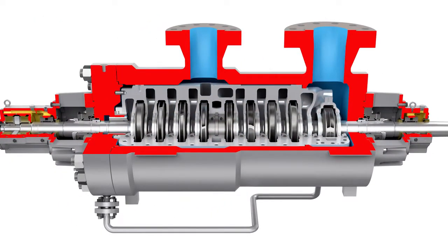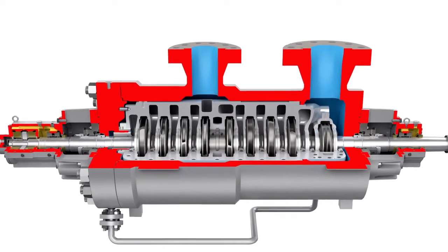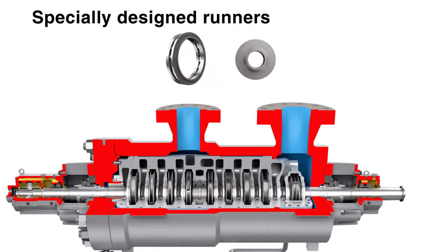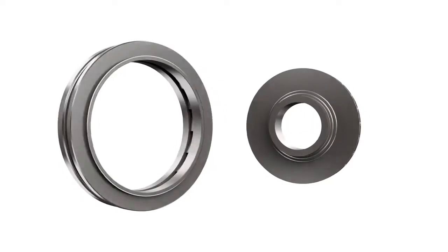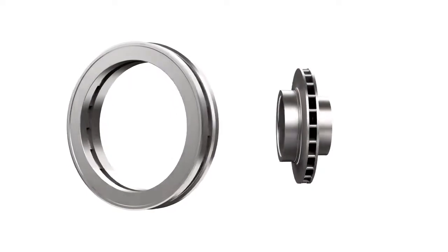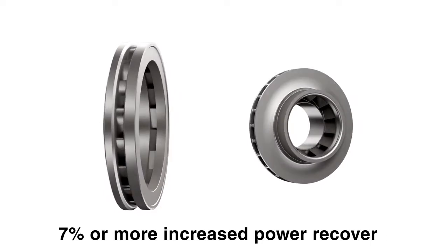Traditional HPRTs, which are essentially pumps running in reverse, may not be able to take advantage of this. But by employing a turbine design that can accommodate the change in volumetric flow rate, operators can recover the additional power in the fluid stream. This optimised turbine is created by replacing impellers with specially designed runners and nozzles. The additional vanes and fluid passages, along with optimised inlets, increase fluid acceleration. This allows for even greater power recovery, often 7% or more, than traditional HPRTs.